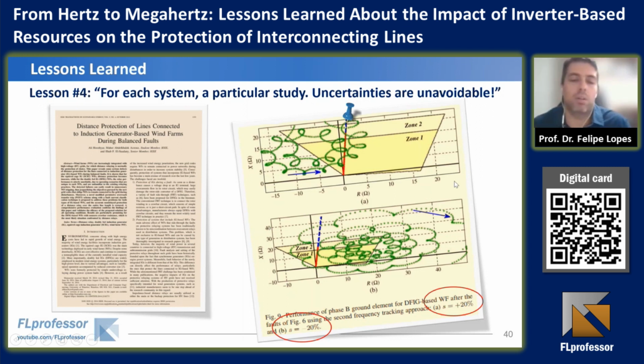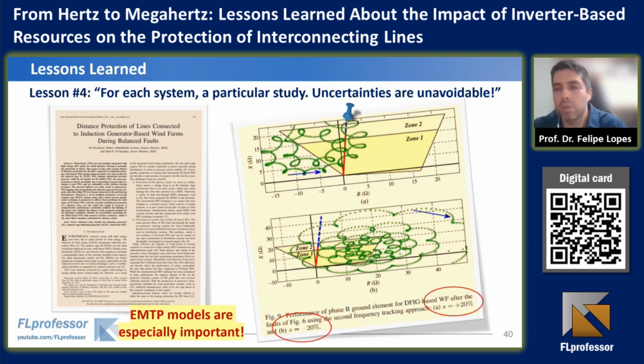And from these results, we can conclude that EMTP models are especially important when we are studying IBRs because these phenomena can only be observed during transient simulations. So it is difficult to verify and to test some of these problems if we consider phasor-based simulations, for instance. And it was a topic addressed in the last Power System Computation Conference that took place in Porto, Portugal. I saw a lot of research groups around the world saying, okay, let's use EMTP to evaluate that, because other programs usually do not reproduce the events properly. So EMTP is very important in this type of study.